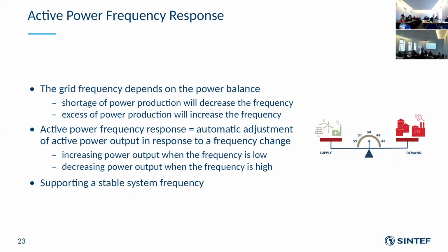The grid frequency is our power balance indicator in the grid. From the frequency, we can read where we're at. Too much power, frequency goes up. Too little power, frequency goes down. The grid codes define this active power frequency response, which is the automatic adjustment that helps with grid-supporting control to stabilize the frequency.